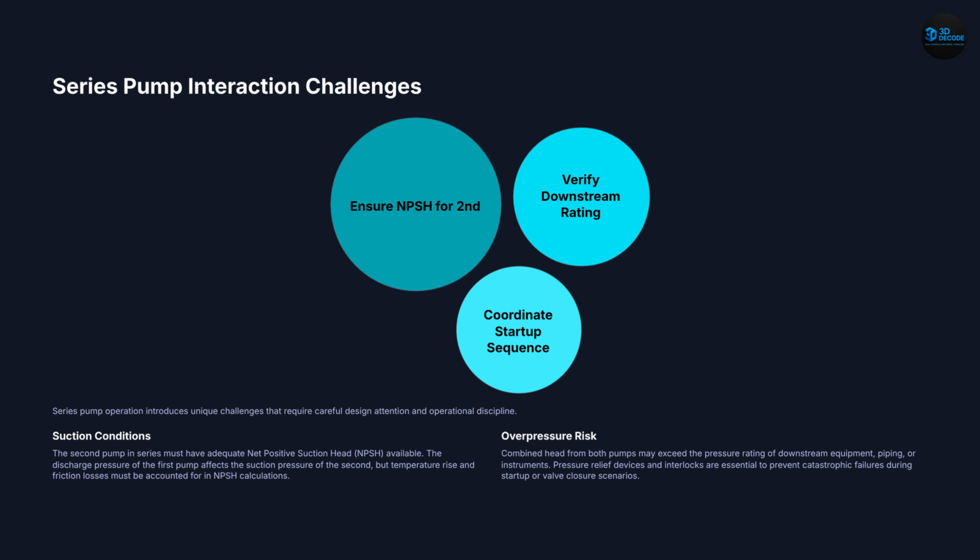Slide 8. Series challenges. In series operation, special care is required. The second pump must have sufficient NPSH available. Also, combined pressure may exceed system limits. Proper pressure relief and interlocks are required.